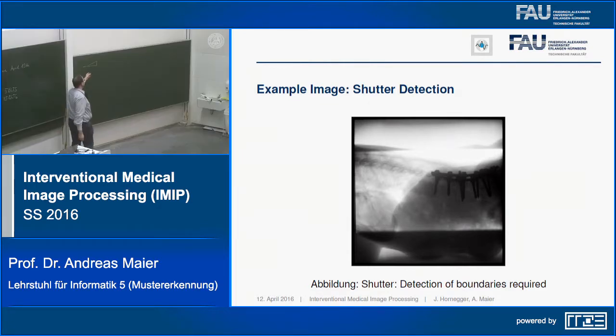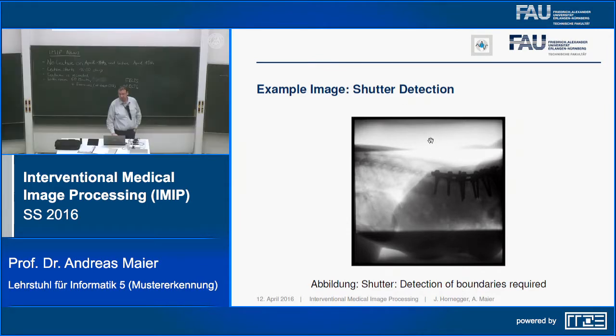These are, of course, on the tube side, so all the X-rays have to pass through here before they hit the patient. And you can use that, for example, to reduce the dose burden for the patient. You can also control the illumination of the image. In this case, you have a lot of direct radiation here, and you can put in this wedge filter to reduce the amount of direct radiation to the detector, giving an image that does not have such a high dynamic range.